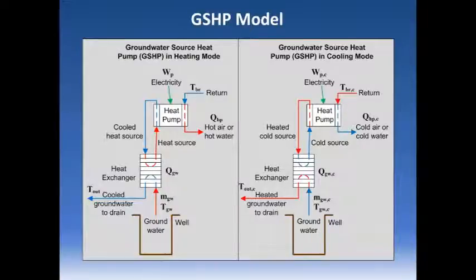What's the sensitivity to the temperature rise, the delta T, and precipitation? Is it a linear relationship? I was impressed by the maybe 3 to 4 gallons per minute flow, so I'm thinking if that's not very much flow, you could increase it and have a lower delta T. You'd have better COP, and maybe less scaling. So I'm wondering how that might factor into precipitation.